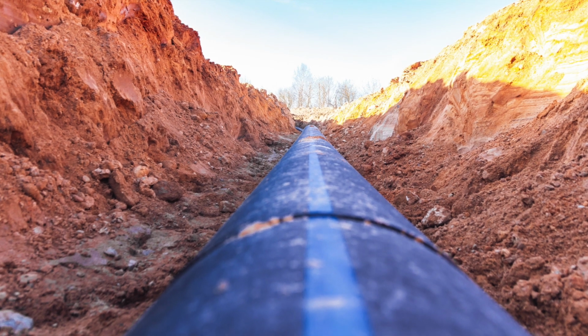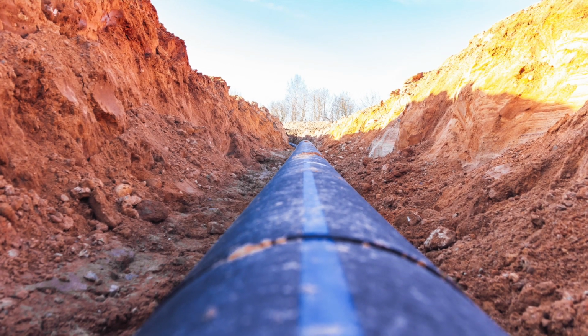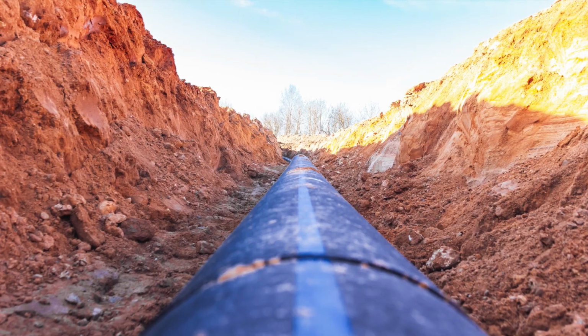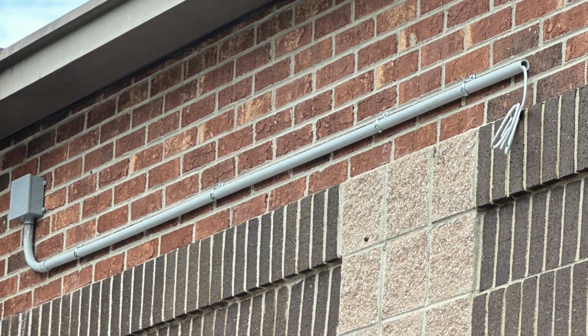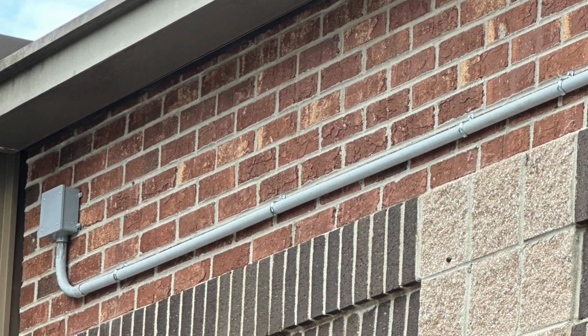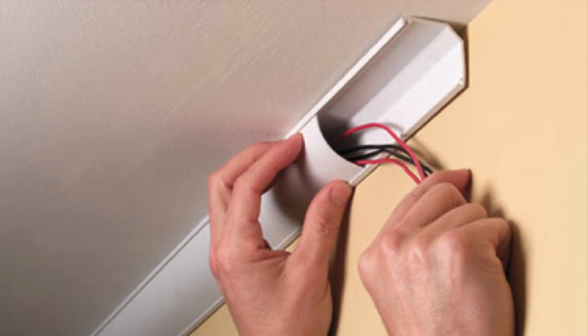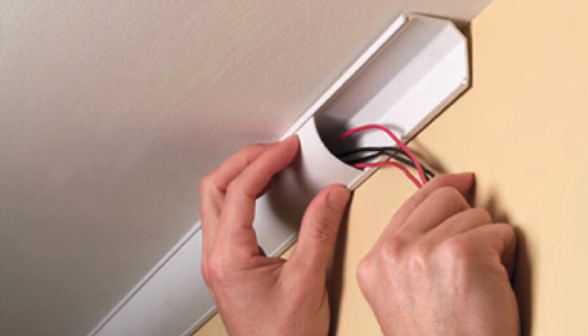Like if we're running to a camera that we're going to mount on a pole in a parking lot, somewhere across grass or dirt, trenching and PVC is kind of underground. That's where we typically use that in low voltage stuff. Now outside of the building, EMT or flex is usually used, or the Panduit or raceway Micah mentioned earlier, that's more for interior hallways, offices, stuff like that.